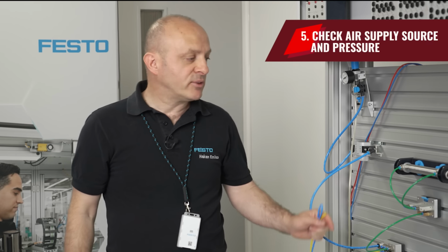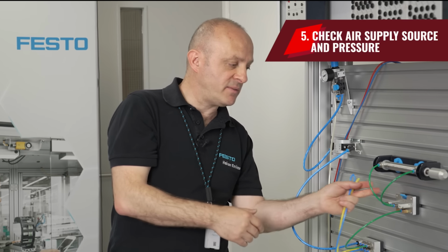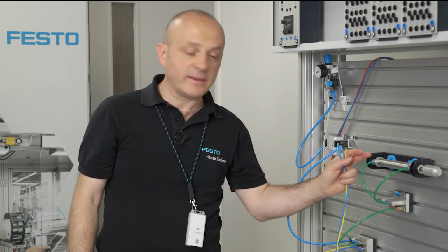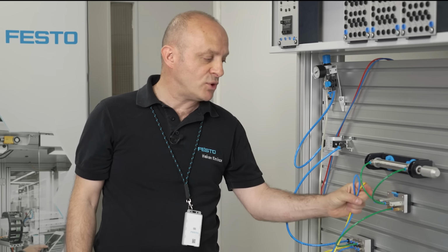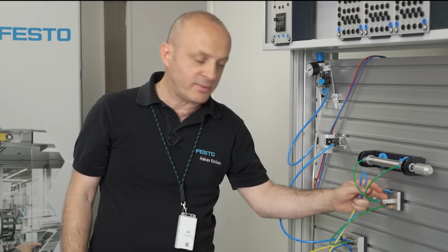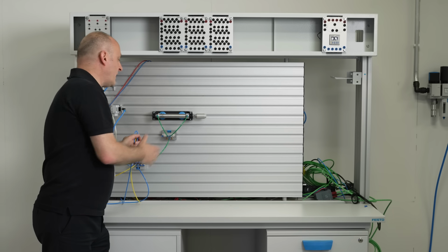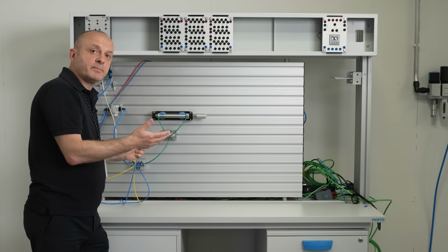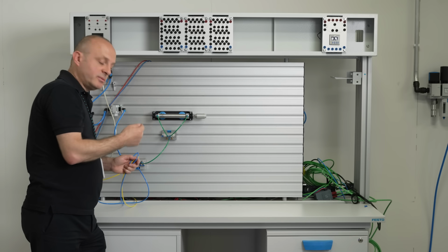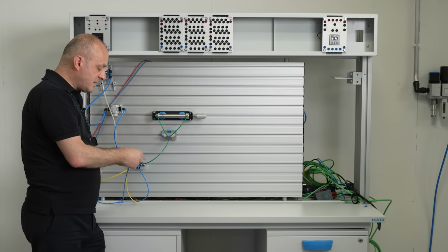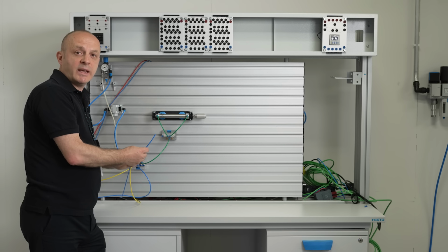This time, we would like to have a look at actuating these valves. We have a 5-2-way valve and a double acting cylinder. This 5-2-way valve is a pneumatically actuated, spring return valve. So let's imagine we have a breakdown, and this cylinder is not advancing. We need to check the actuation. Actuation is pneumatic. So let's imagine I've got this tube, and air is coming out.